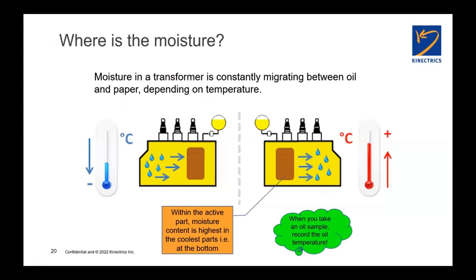The moisture inside a transformer is constantly migrating. I call it moisture partitioning. It's constantly migrating between the oil and the paper, and that is a temperature driven process. So as the temperature drops, moisture is going to want to come out of solution from the oil, and it's going to get pulled into the paper, as we see in the diagram on the left. As the temperature rises, conversely, moisture is going to get pushed out of the paper and it's going to get absorbed into the oil. And so we see a shift of moisture from the paper into the oil.